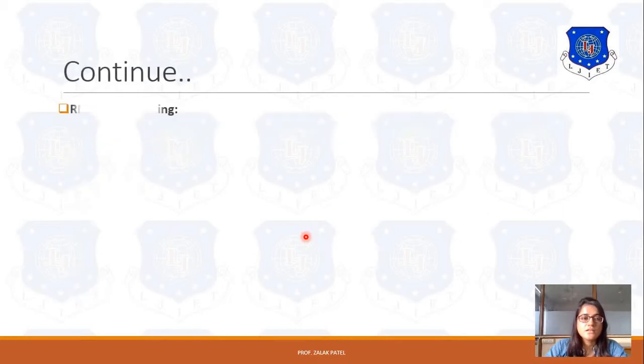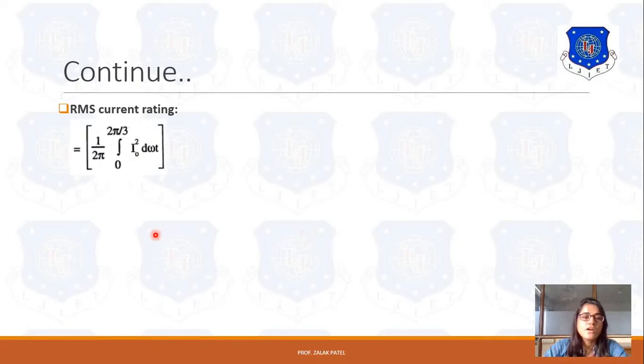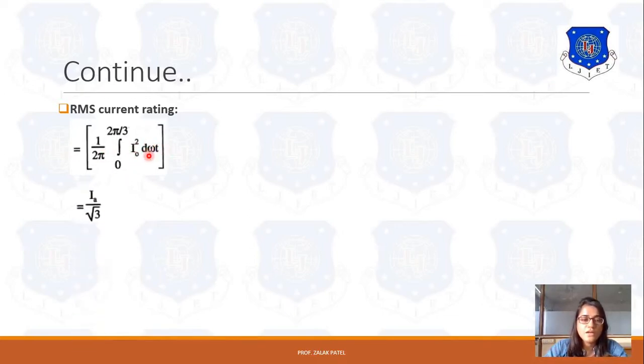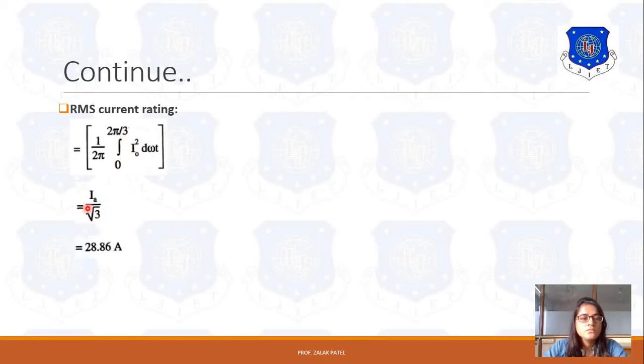Now let's consider the RMS current rating. RMS is 1 upon 2pi, integrated from 0 to 2pi/3, of I0 squared d(omega t). Since the root mean square value must be taken, it is I0 upon root 3. If we put the values, then it is 28.86 ampere for RMS current rating.